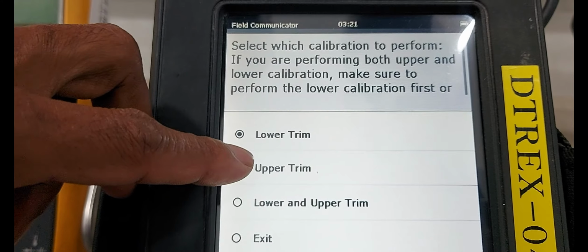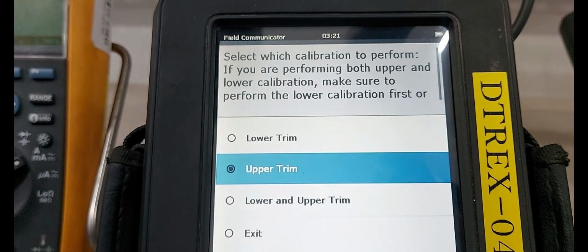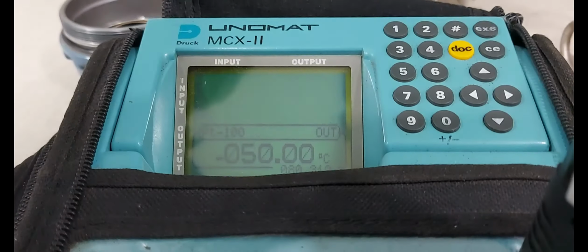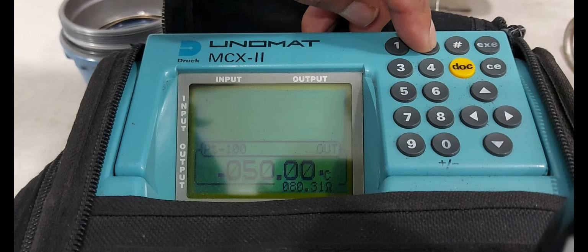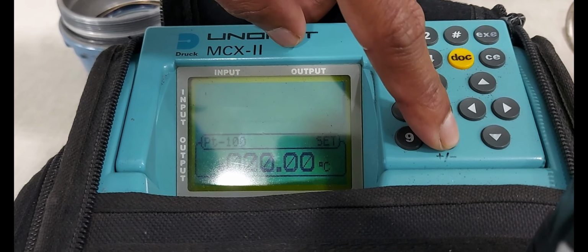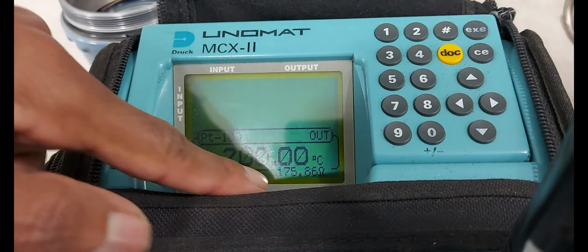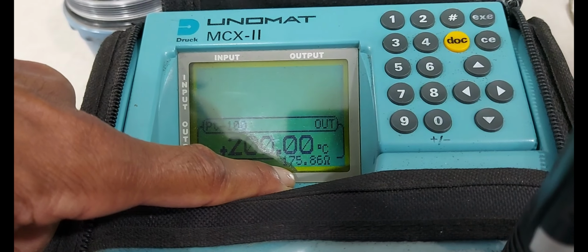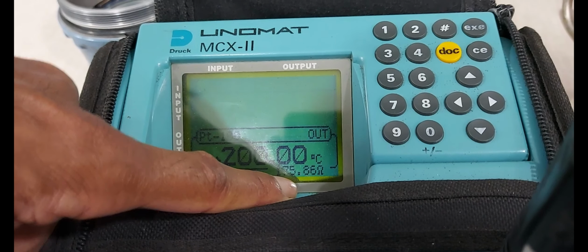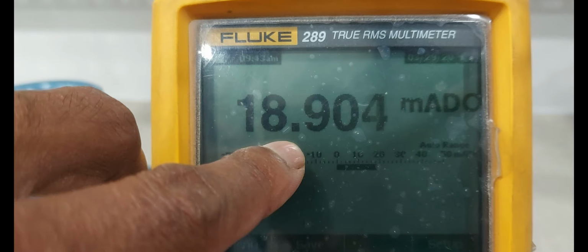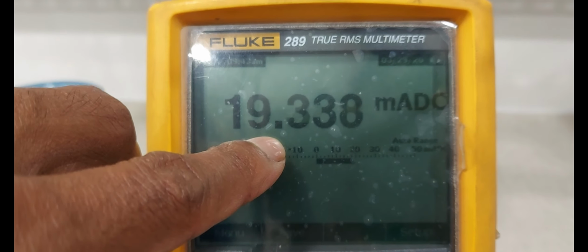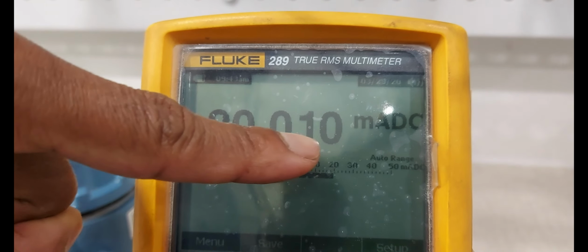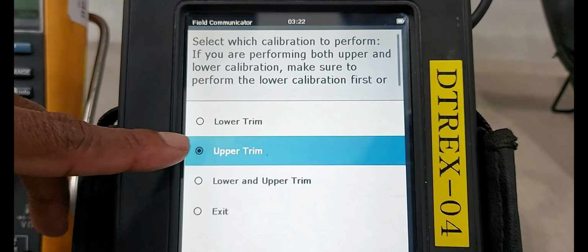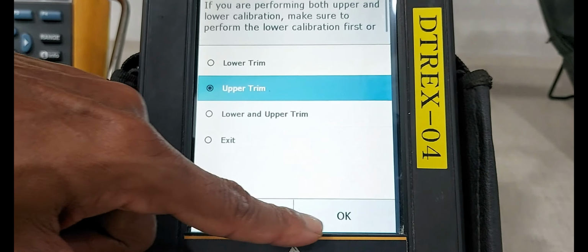Next we are doing the upper sensor trim. Select the upper sensor. Set the temperature 200 degree. 200, enter. The resistance showing 175.86 ohms. Now milliamps showing up. Now output is stable. Next we are selecting the upper trim, then OK.